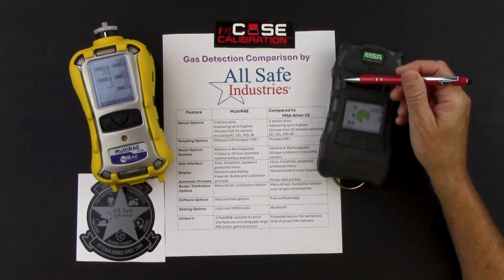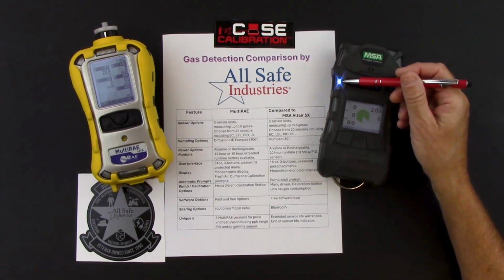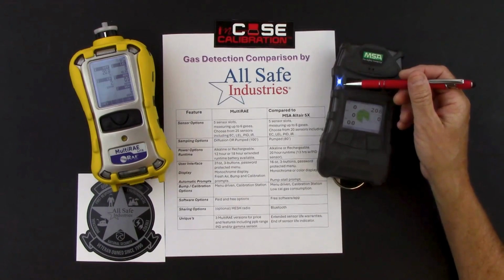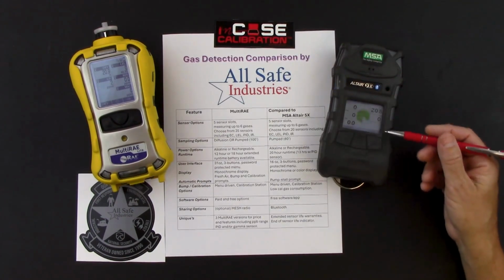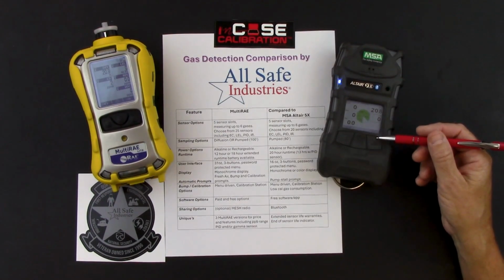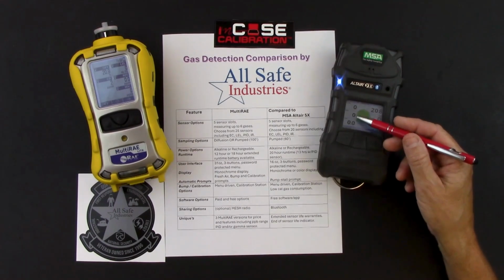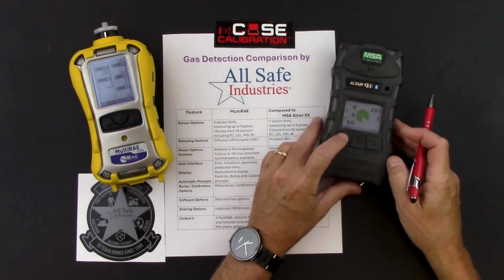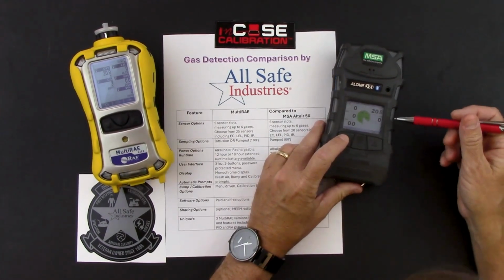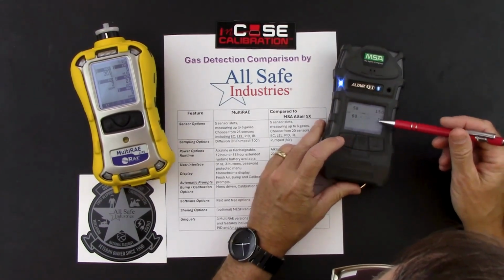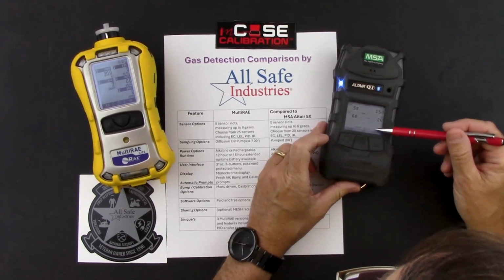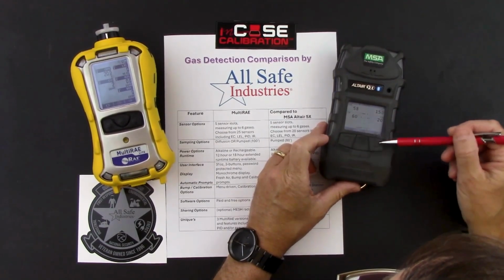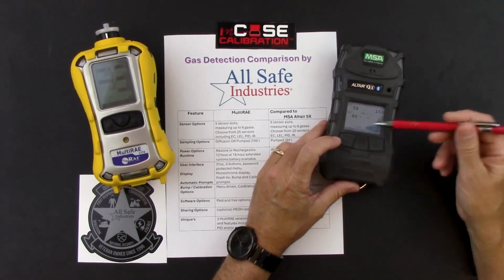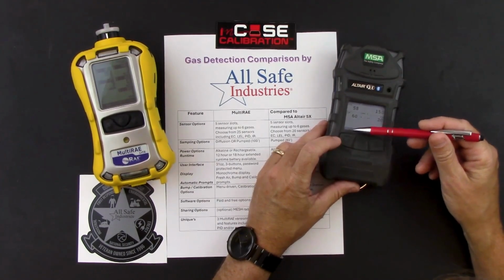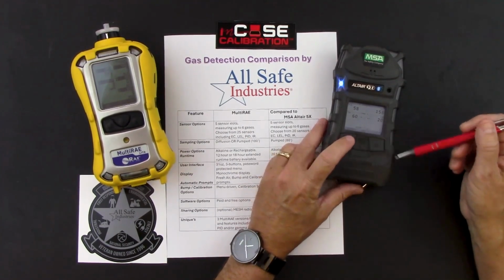You can also see the blue light flashing because it's waiting to connect to that app that you could download to your cell phone. So again, I'm not going to calibrate right now. If I wanted to run a bump test, I could by pressing the down arrow button, and then it would give me the prompts to begin the bump test. So bump test, question mark, yes or no, and I would hit the appropriate button. You can see what's coming next by the menu here on the down arrow button.